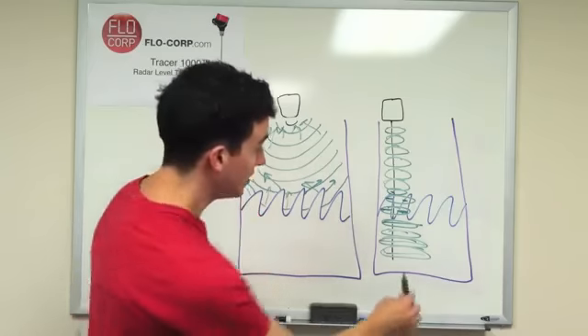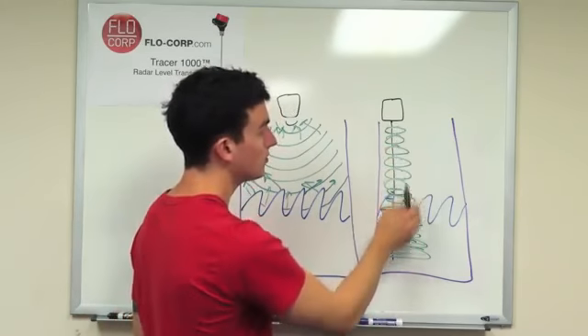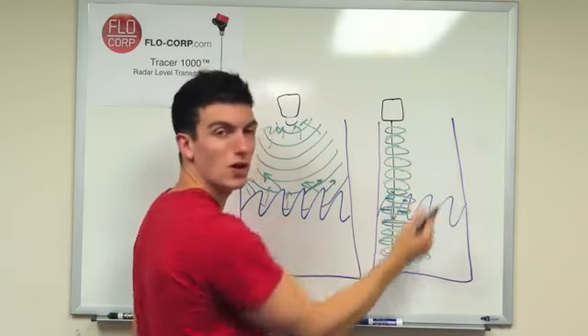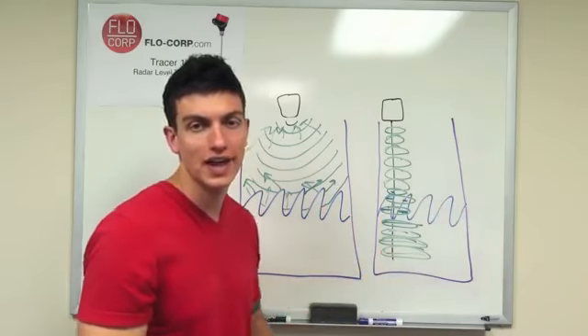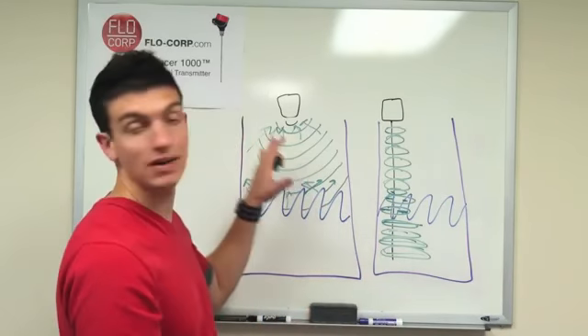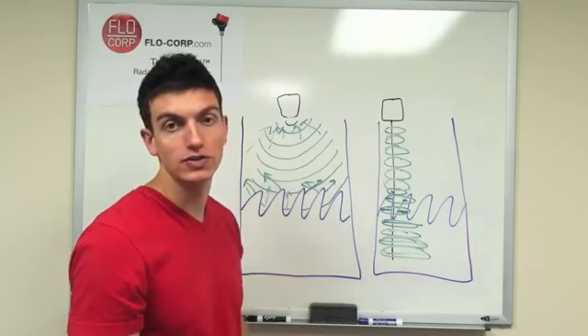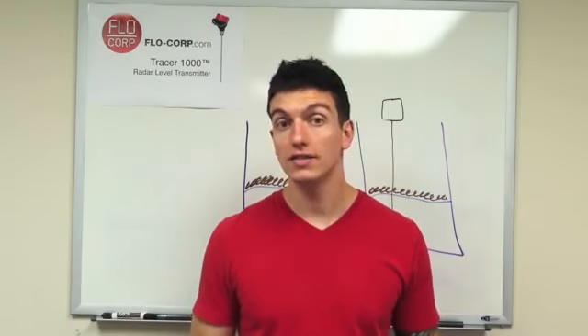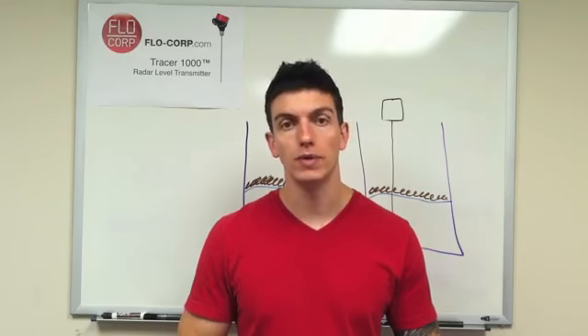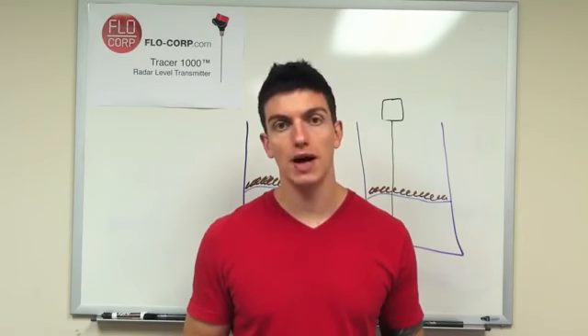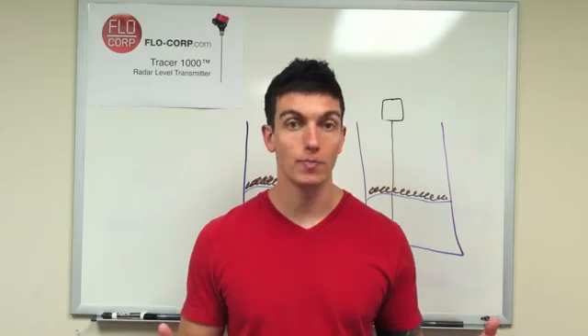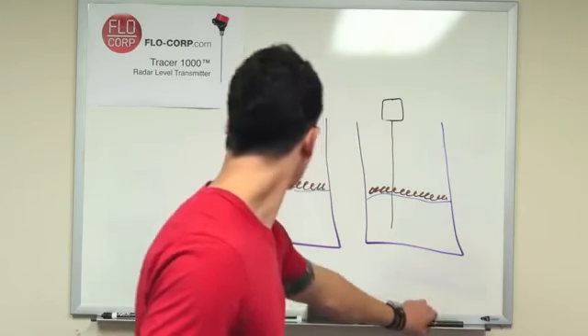So the signal returns straight up through the probe, so there's no reflection off the side walls of the tank that are problematic the same way that is problematic for ultrasonic. The third process condition I want to talk about is foam. How does ultrasonic respond compared to guided wave radar in foam? So we'll take a look here.